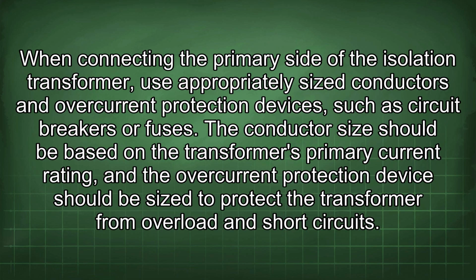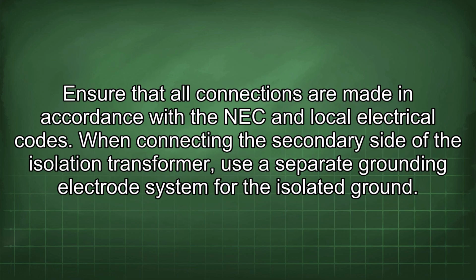When connecting the primary side of the isolation transformer, use appropriately sized conductors and overcurrent protection devices such as circuit breakers or fuses. The conductor size should be based on the transformer's primary current rating, and the overcurrent protection device should be sized to protect the transformer from overload and short circuits. Ensure that all connections are made in accordance with the NEC and local electrical codes.